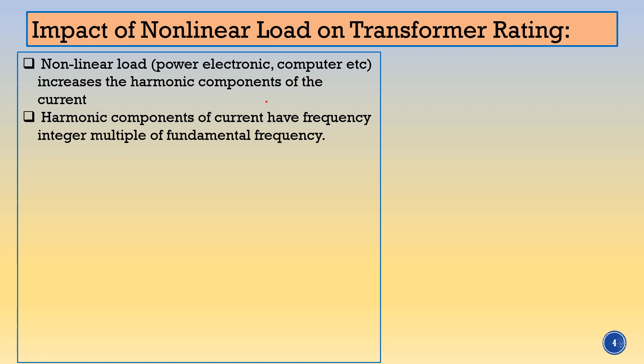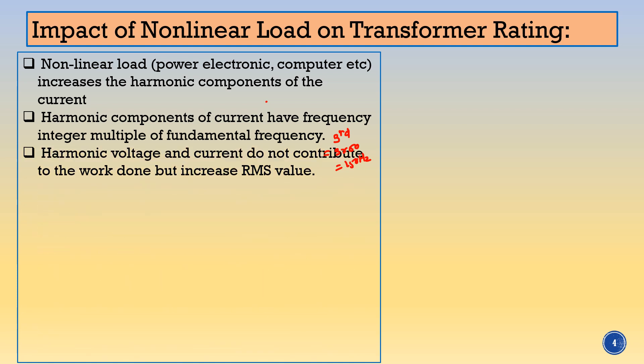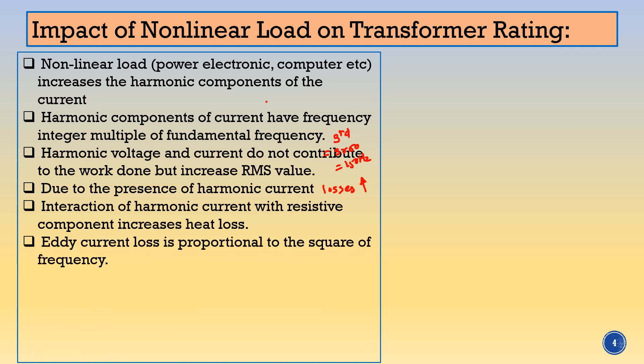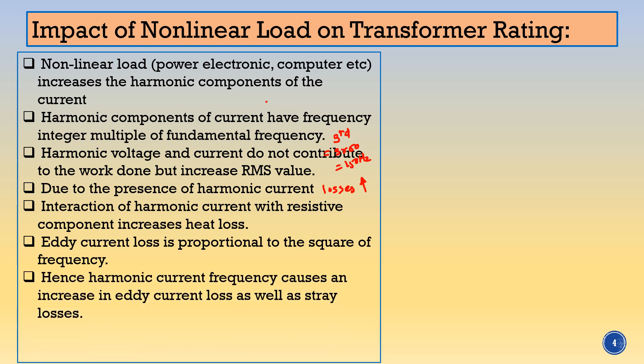For third harmonics, the frequency will be 3 × 50 = 150 Hz. It is the integer multiple of fundamental frequency. The harmonic voltage and current do not contribute to any work done, but they increase the RMS value of the current. Due to the presence of this harmonic current, losses are going to increase because the RMS value of the current increases. The interaction of the harmonic current with the resistive component increases the heat losses. Eddy current loss is proportional to the square of frequency.